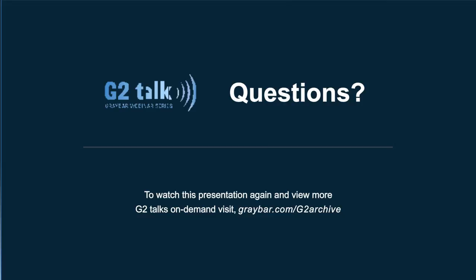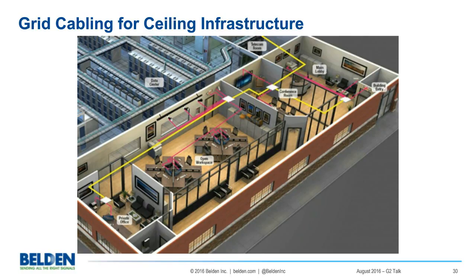The first question is around structured cabling standards: does utilizing direct connect violate structured cabling standards? That's a good question, and the answer is no, it does not, especially if you're using grid cabling, as I'm showing here. You're still bringing connectivity out to a zone box, and then from that zone box to your end device. That's still a structured cabling scenario, and the purpose of structured cabling is to allow you to put things together and change them easily in the future. This grid cabling approach does not violate that.